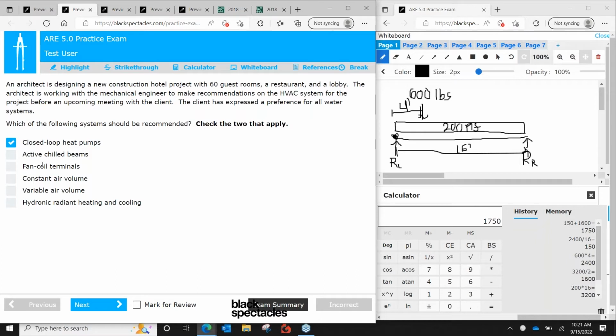Because each fan coil is pulling in outdoor air, this needs to be located on an exterior wall. Not having to duct air around the building does save space. However, the humidity of the air cannot be easily controlled because you're mixing in outdoor air and existing room air. Each fan coil terminal is individually controlled, adjusting the flow of water to the pipes. This is therefore a good choice for our hotel since it provides individual control and is an all-water system.